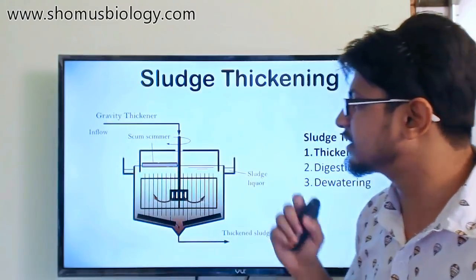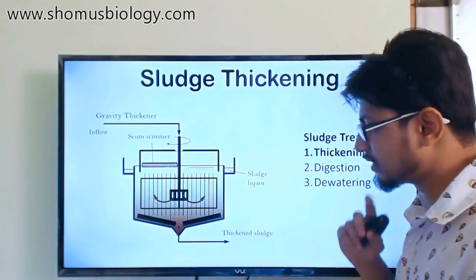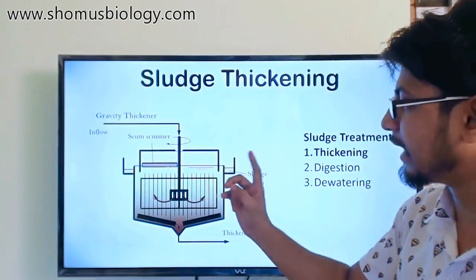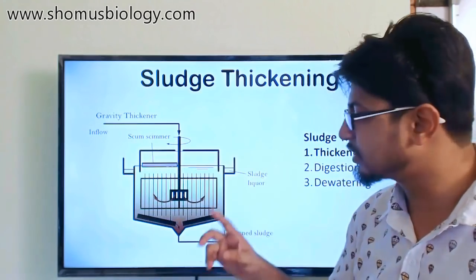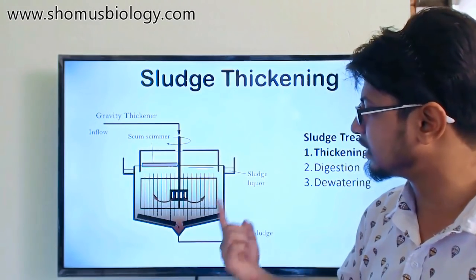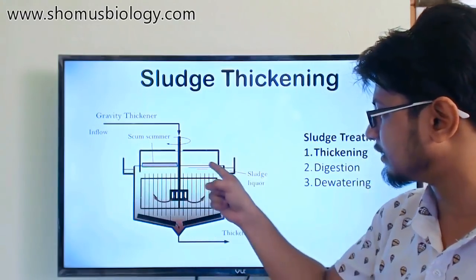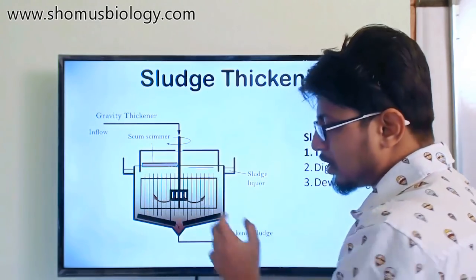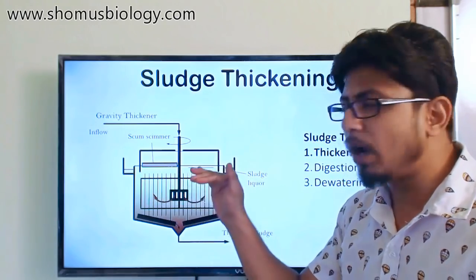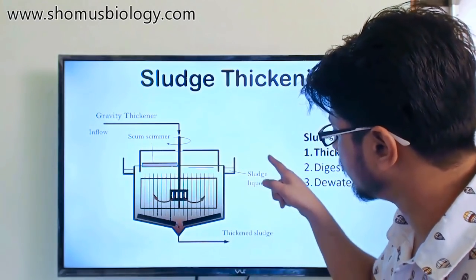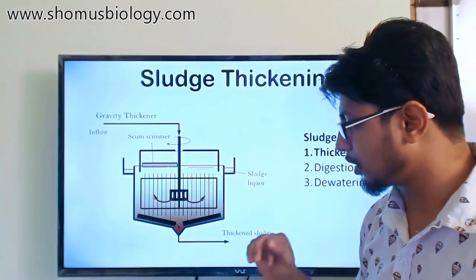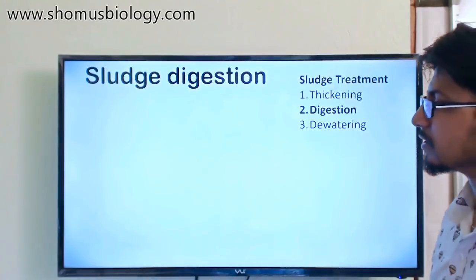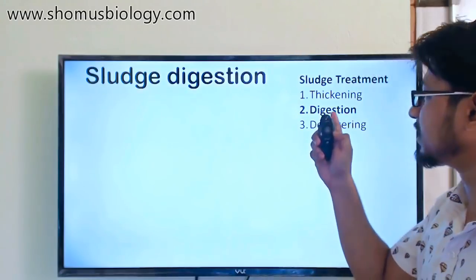The first step is thickening of the sludge, done using a gravity thickener. The gravity thickener has a small, slowly rotating grill-shaped unit. As it rotates, the water content of the sludge is transferred out as sludge liquor, while the solid compounds settle to the bottom as thickened sludge. That is how the gravity thickener works to condense the sludge before the next stage.